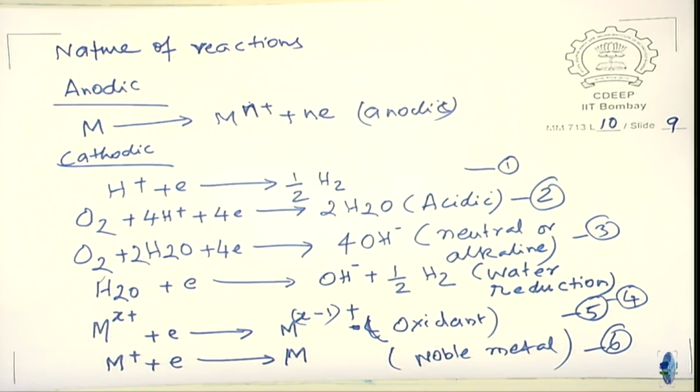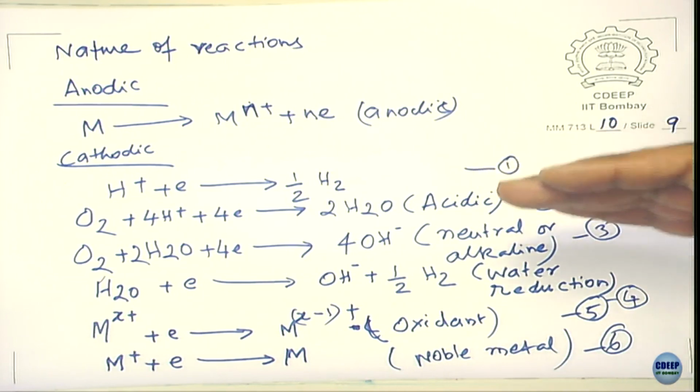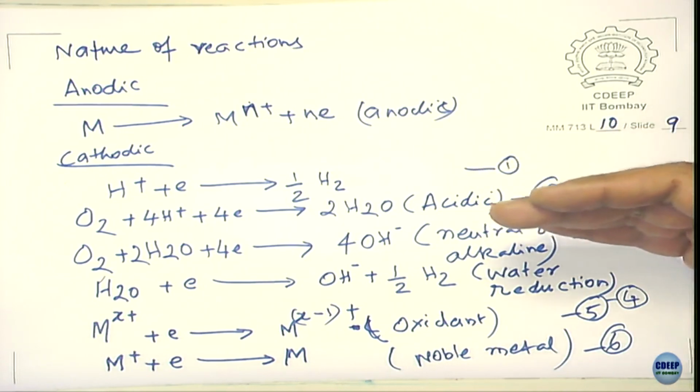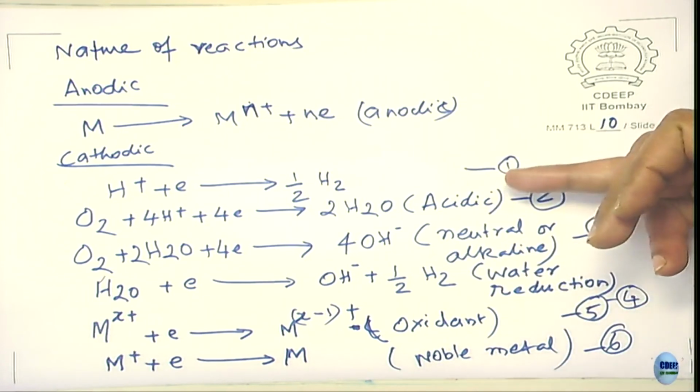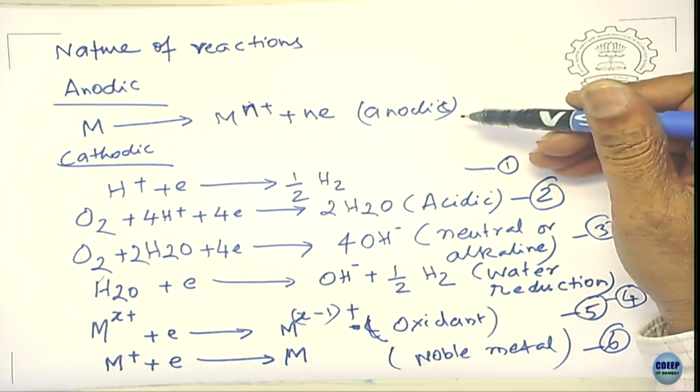How you remove oxygen and all, let us not discuss right now. That is a boiler, a separate subject altogether. But this is how the principle is. The principle is to remove the species responsible for the cathodic reaction, stage 1. So, make the pH alkaline, remove the oxygen content, and so the corrosion rate of the boiler stops on the cathodic side. And the anodic side, what can you do?